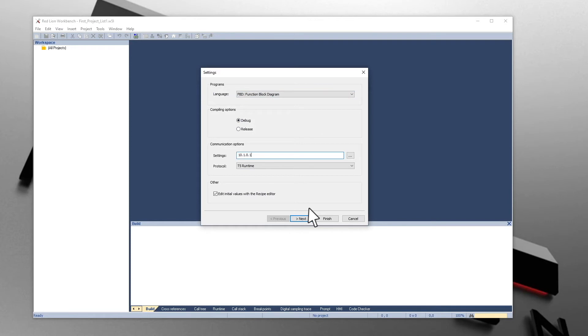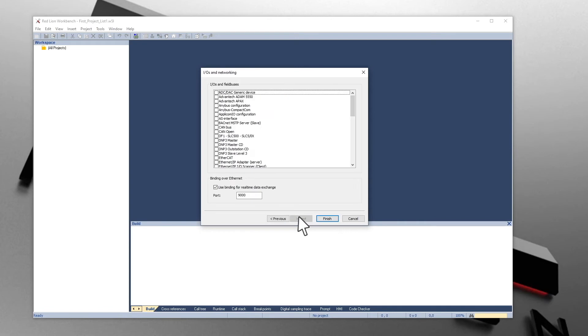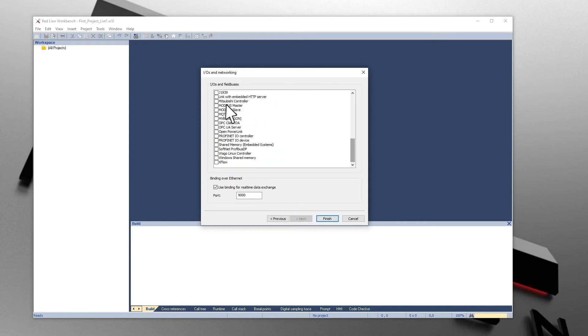Under Communications, set the IP address for the RTU. We'll match the IP address of Interface 1 in the RTU configuration. Then, select T5 Runtime. In the protocols list, we'll select Modbus Master so we can query the slave EtherTRAC2 module.